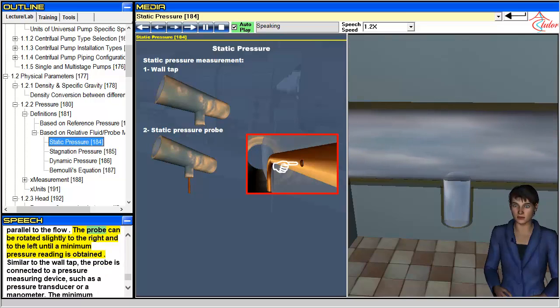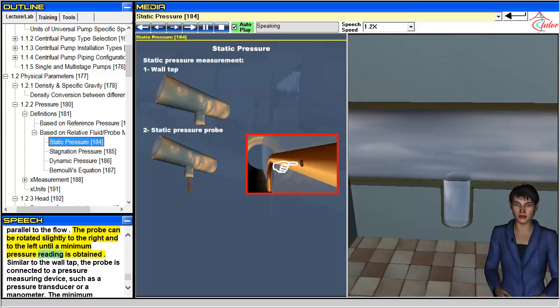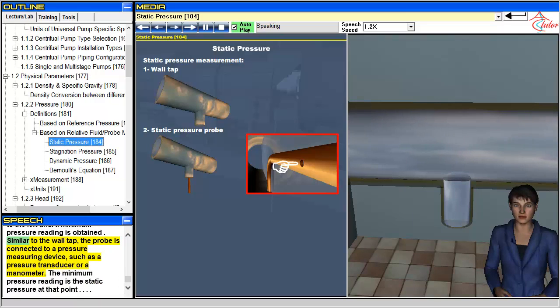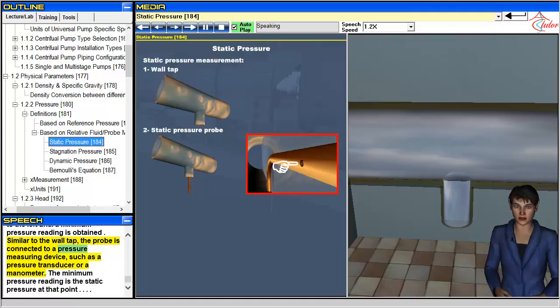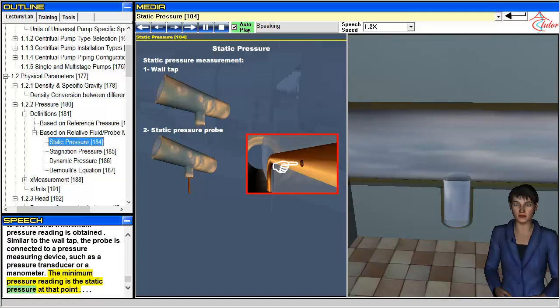The probe can be rotated slightly to the right and left until a minimum pressure reading is obtained. Similar to the wall tap, the probe is connected to a pressure measuring device such as a pressure transducer or manometer. The minimum pressure reading is the static pressure at that point.